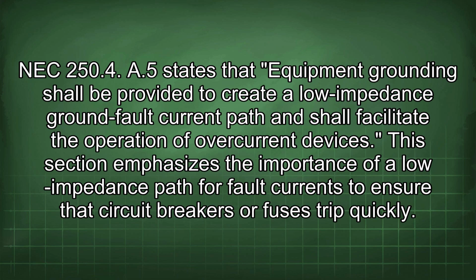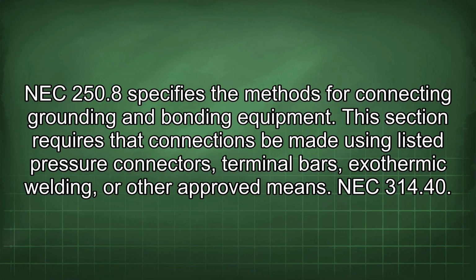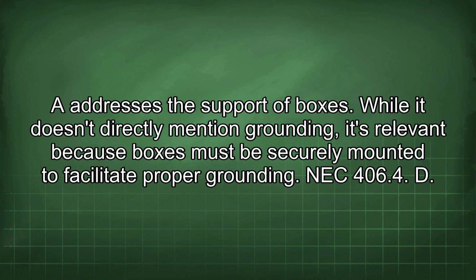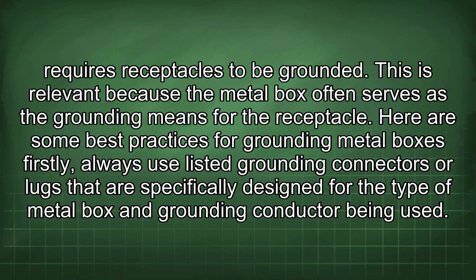This section emphasizes the importance of a low impedance path for fault currents to ensure that circuit breakers or fuses trip quickly. NEC 250.8 specifies the methods for connecting grounding and bonding equipment. This section requires that connections be made using listed pressure connectors, terminal bars, exothermic welding, or other approved means. NEC 314.40 addresses the support of boxes. While it doesn't directly mention grounding, it's relevant because boxes must be securely mounted to facilitate proper grounding. NEC 406.4(D) requires receptacles to be grounded. This is relevant because the metal box often serves as the grounding means for the receptacle.